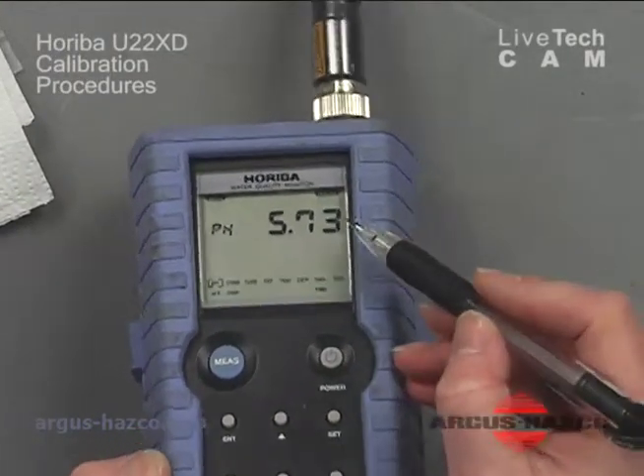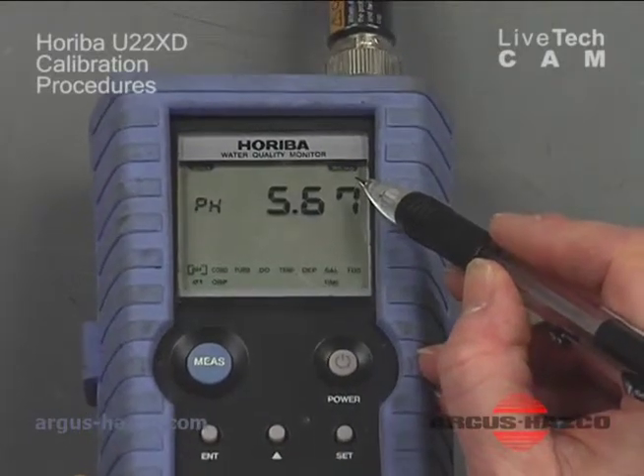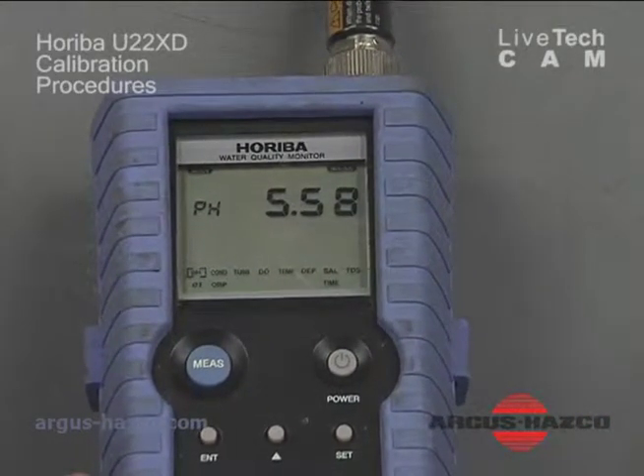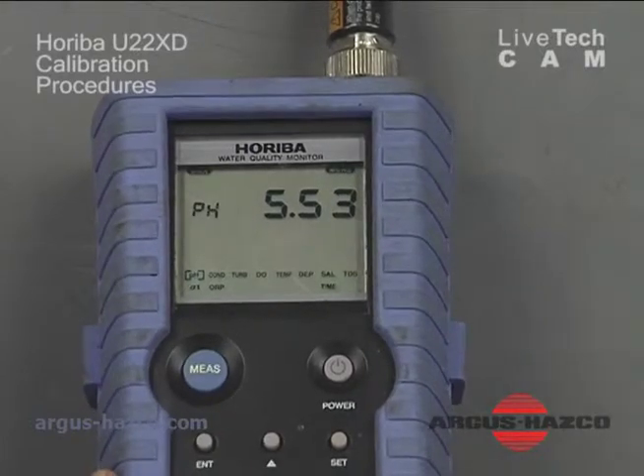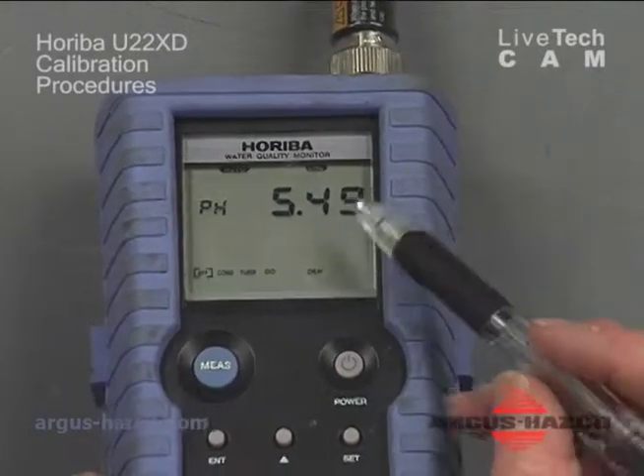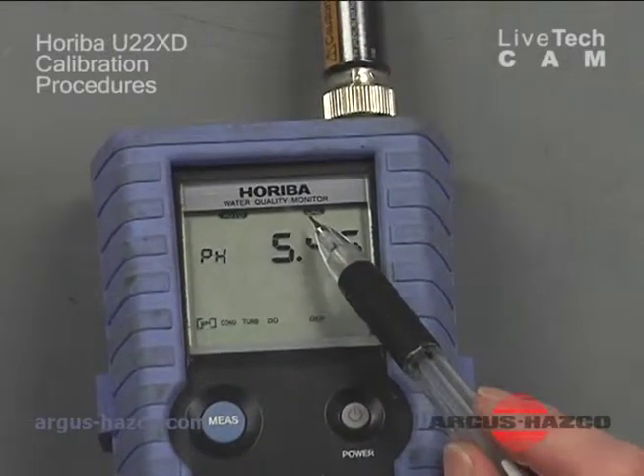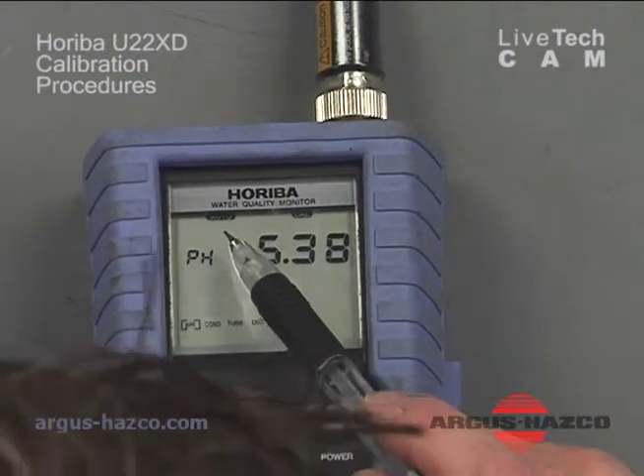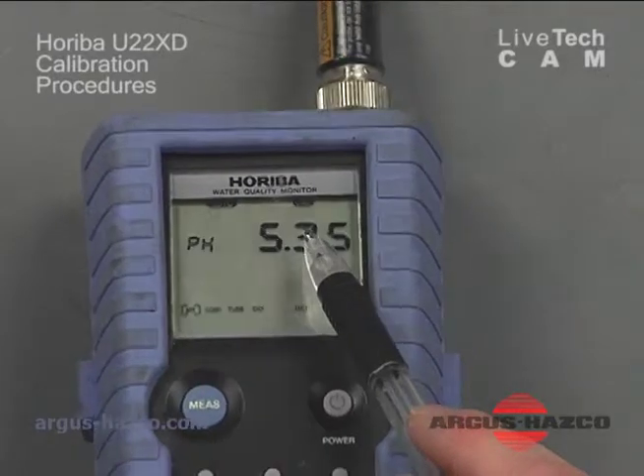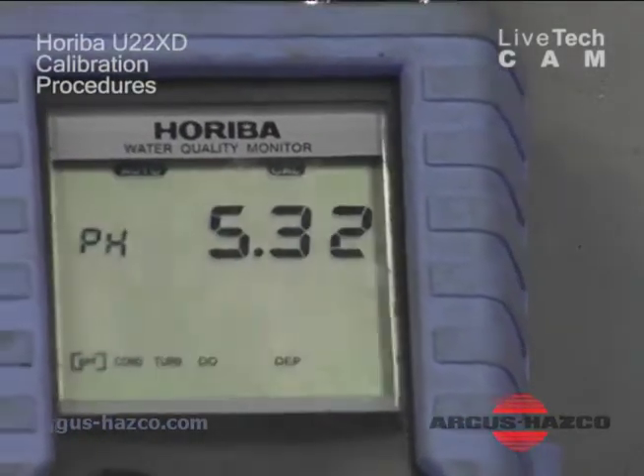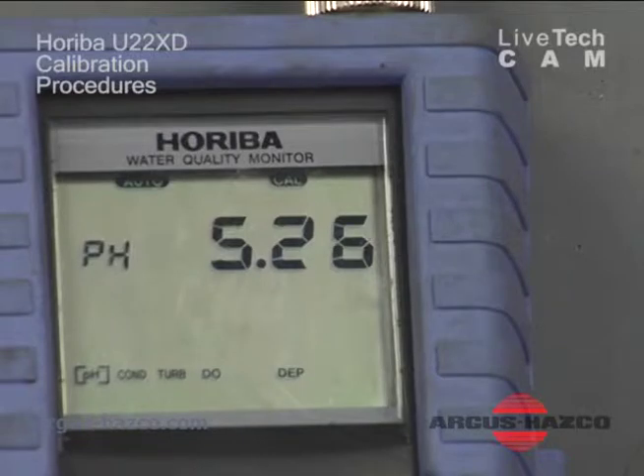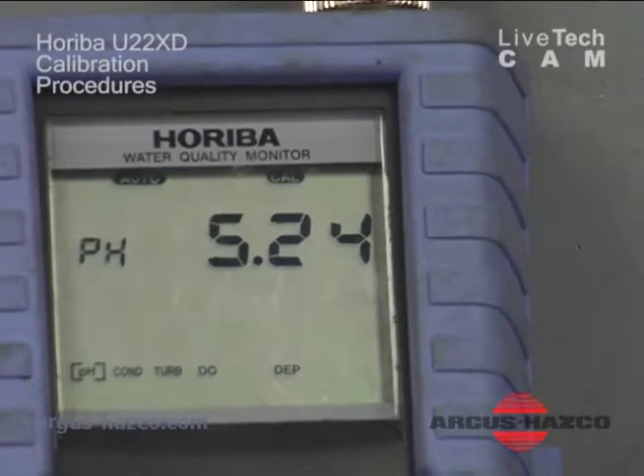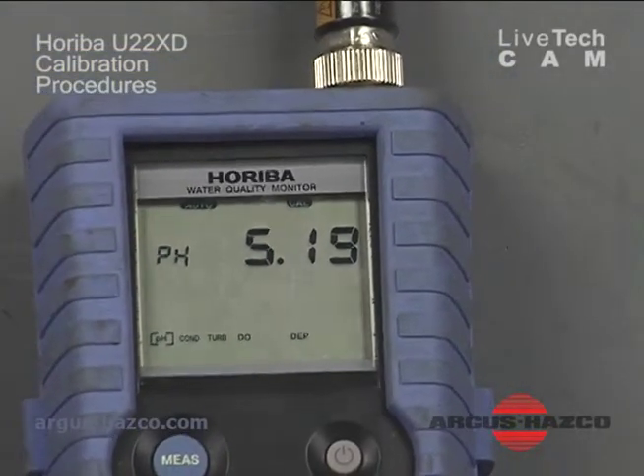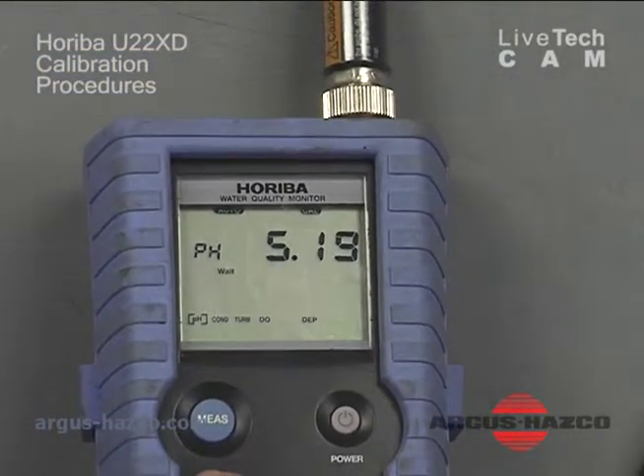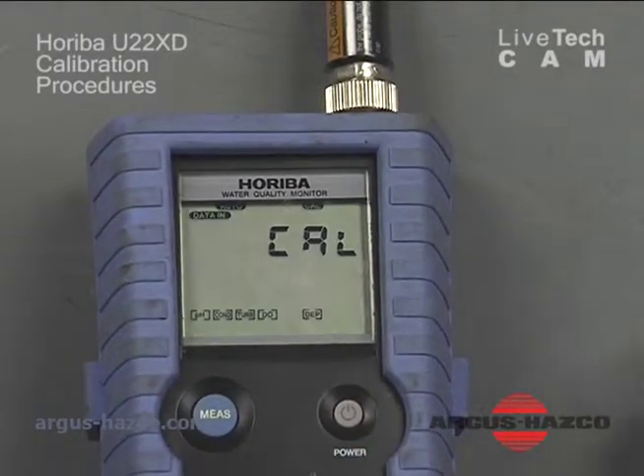And if you look up in the upper corner here, we'll see the different modes that the unit is in. So if I hit my cal key, I don't know if it'll say auto and then cal. It's really hard to see. And when I'm in that mode, then I go ahead and hit my enter key to start my calibration procedure.